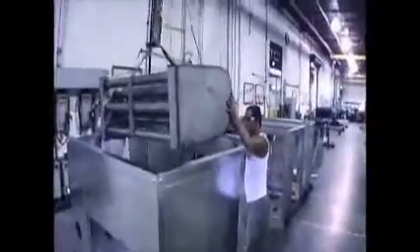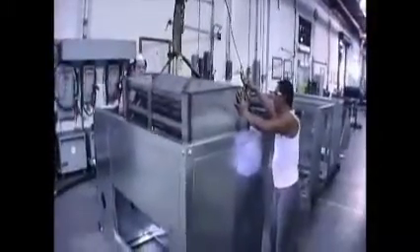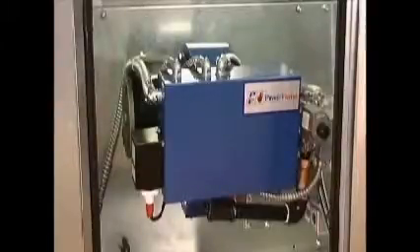So we have a unit that at its very essence has the ability to handle 4 levels of filtration, an 8-row coil, a 2-row reheat coil, plus a very high efficiency gas-fired burner. We were looking for this very high turndown opportunity. If you were to just go by the standards, you could set your unit up for high fire, you could set your unit up for low fire, and as long as you're clean at those 2 points, they allow you to claim that as your turndown. We're not comfortable with that. We want, from high to low, clean the entire range.